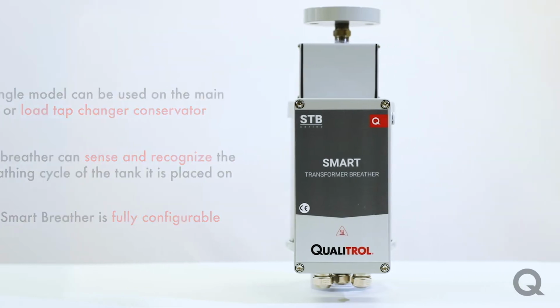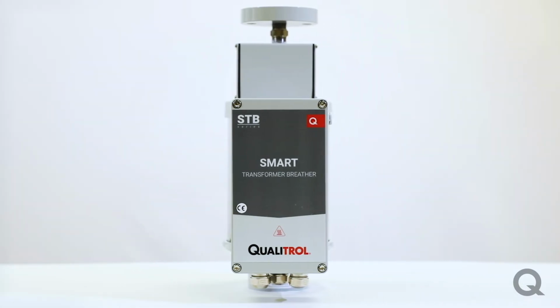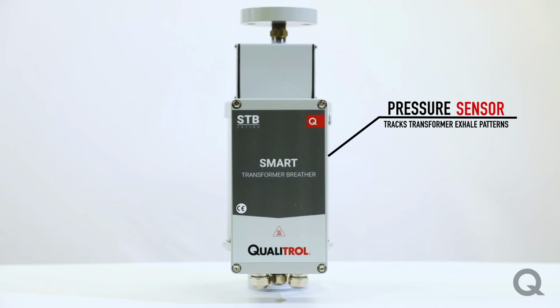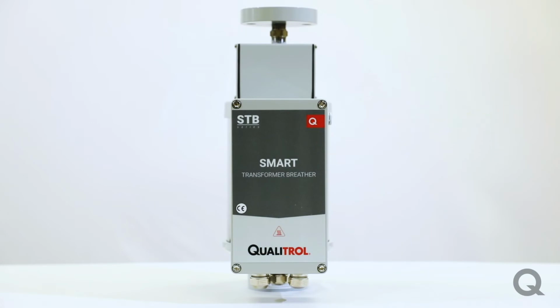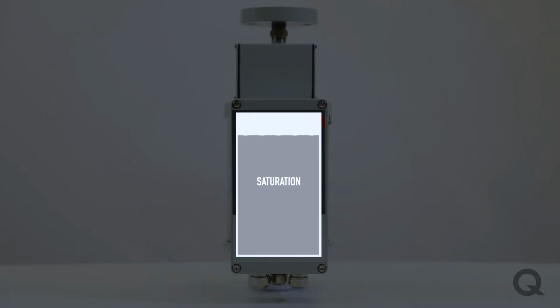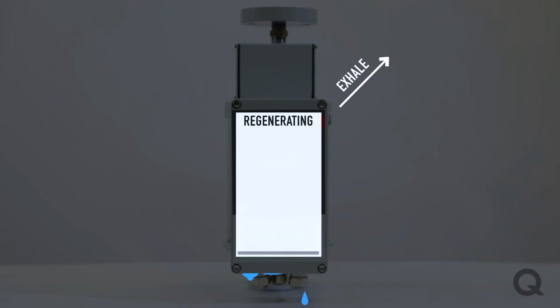Our breather operates on the principle of monitoring the saturation level of the desiccant. It also uses a pressure sensor to determine the best time to regenerate by tracking the transformer's exhale patterns. When the breather senses that the desiccant needs to be regenerated, it'll wait for an exhale cycle and it'll initiate the regeneration process during that cycle.